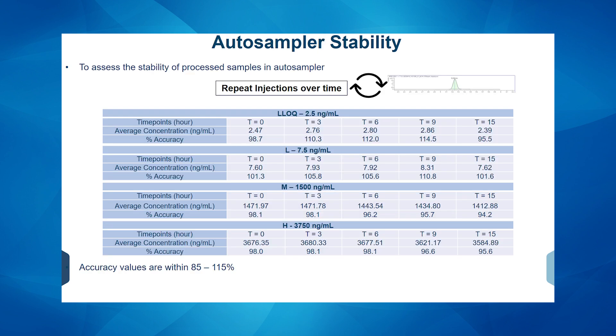Once samples are prepared, they are ready to be placed in the auto-sampler. Because your sample sequence includes calibration standards and QCs, it is very important to ensure that samples sitting in the auto-sampler remain stable during that time. A sample sequence would include calibration standards, QC samples, and prepared samples. We created quality control samples at four different concentration levels and calculated accuracy at each time point. We conducted this study for 15 hours and determined that all accuracy values were within 85 to 115 percent.